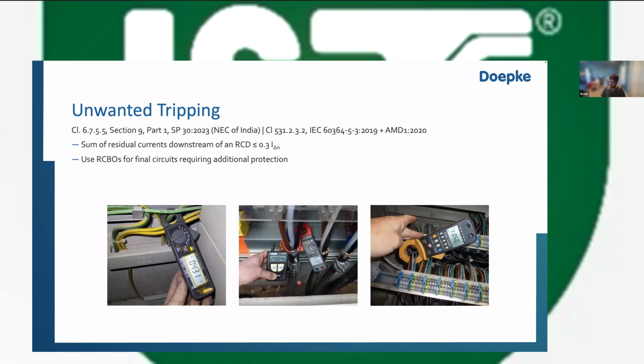How do we deal with unwanted tripping? So basically, there are a couple of things. One thing is the frequency, but the other thing is making sure the RCD is not overloaded, essentially. The important thing is that the sum of residual currents downstream of an RCD should not exceed 0.3 times the rating of the RCD. So for a 300 milliampere device, we know this because it's sold a lot in the elevator industry, 300 milliamperes into 0.3 is 90 milliamperes. So you cannot have more than 90 milliamperes of leakage current connected to one 300 milliampere RCD.